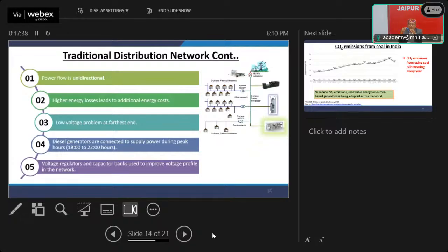And I still remember, my mother used to say at 5:45, switch on the tube light, switch on the tube light. She used to shout at us. What is the reason? Because if you do not switch on the tube light before 5:30, here 5:45, 8 o'clock, it is next to impossible because of the low voltage. But today, if you go to cities like Mumbai, Chennai, or Delhi, you will find small capacitor banks being placed at each and every pole, to compensate for voltages.